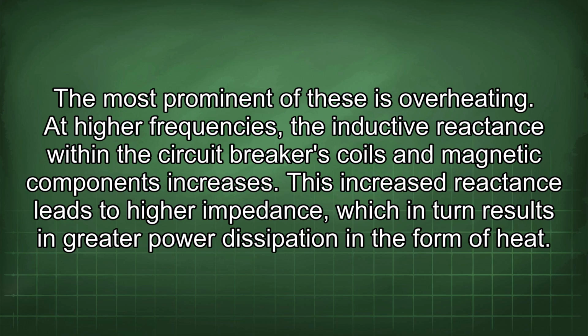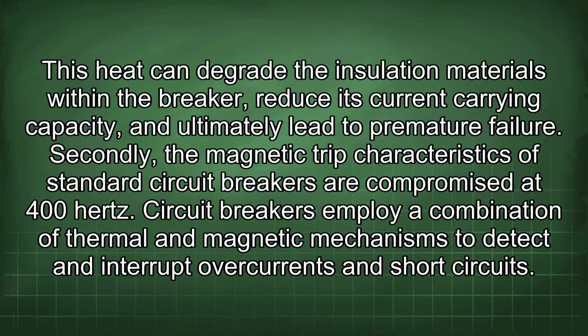At higher frequencies, the inductive reactance within the circuit breaker's coils and magnetic components increases. This increased reactance leads to higher impedance, which in turn results in greater power dissipation in the form of heat. This heat can degrade the insulation materials within the breaker, reduce its current carrying capacity, and ultimately lead to premature failure. Secondly, the magnetic trip characteristics of standard circuit breakers are compromised at 400 Hz.